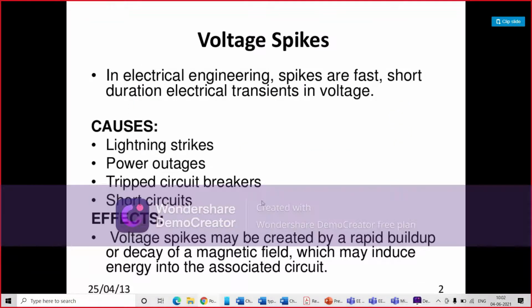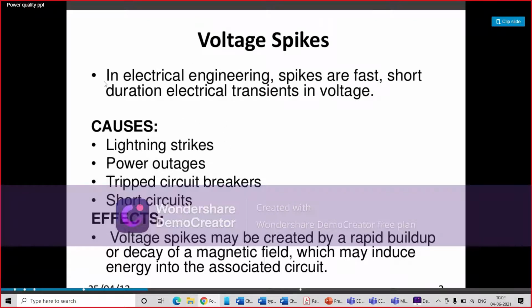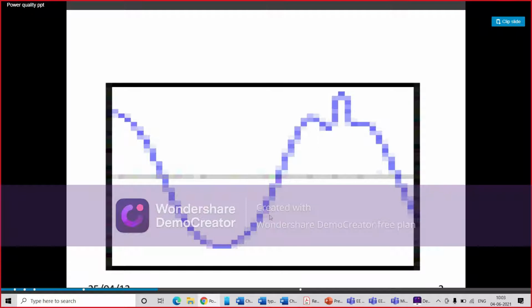Voltage spike. So after your long term interruption, you have these voltage spikes. What does that mean? In electrical engineering, spikes are fast, short duration electrical transients in voltage. So they are basically transients, and their nature is that they are fast and of short duration. What could cause voltage spikes? Lightning strikes, power outages, tripped circuit breaker, short circuit. All these are the causes of your voltage spikes. And these voltage spikes may be created by a rapid buildup or decay of a magnetic field, which may induce energy into the associated circuit, and this energy could lead to many more consequences. It is like this. This is a normal wave, and here you are having the spike. So this is a voltage spike. This is showing the spike.